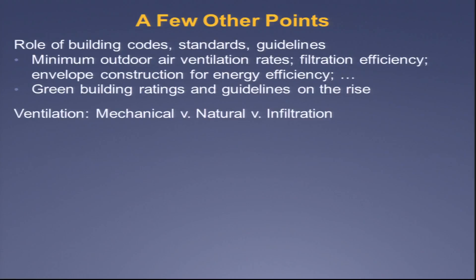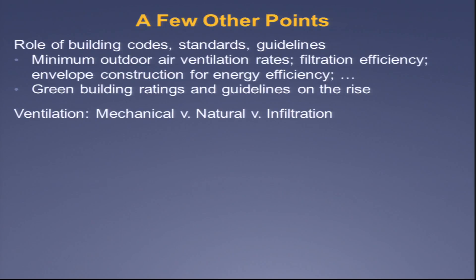Ventilation is something I've done a lot of work in. This came to my head yesterday when Brent was talking — the whole issue of mechanical ventilation, natural ventilation, and infiltration. Buildings with mechanical ventilation may have a known and controlled amount of outdoor air intake, and they may have filtration that is able to remove from the air some of the stuff we care about. I wouldn't bet on either of those happening, but there's a possibility of controlled outdoor air entry and filtration. Natural ventilation — I don't know if the rates are higher, lower, or the same as a mechanically ventilated building. I have never seen a measurement of a ventilation rate in a naturally ventilated building that I've been comfortable with.